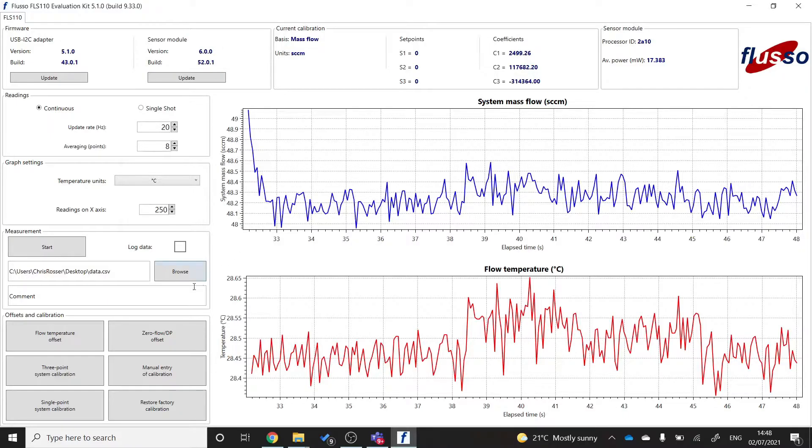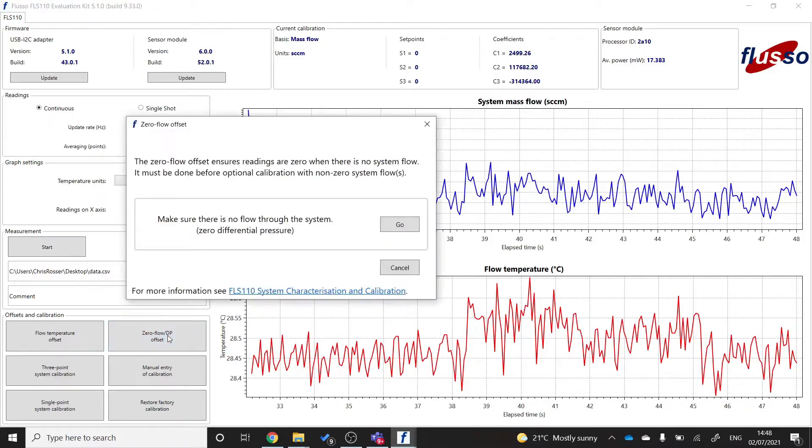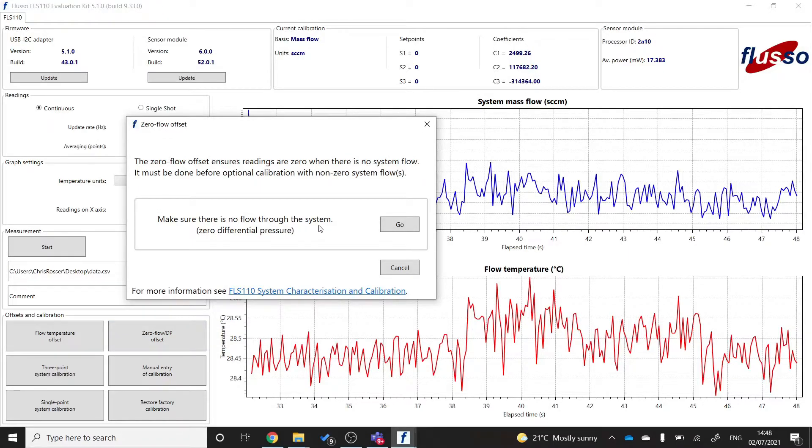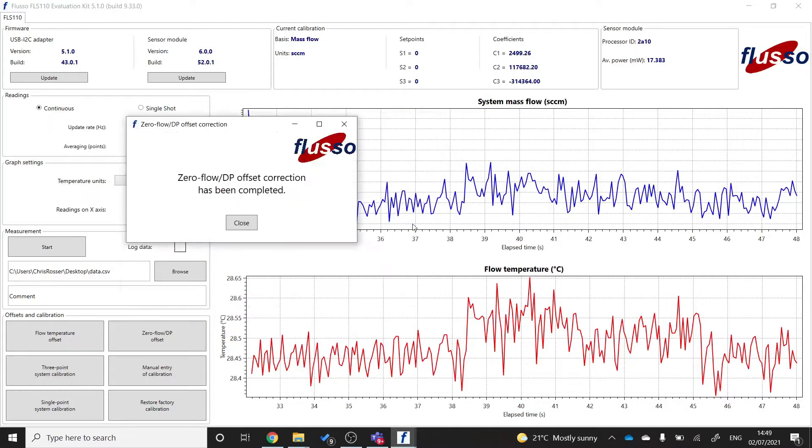Then you'll want to make sure you have zero flow through the sensor and you'll want to do a zero flow offset correction. Obviously, just confirm that you've got no flow through the system and zero differential pressure across the sensor. Click go. And that will complete.